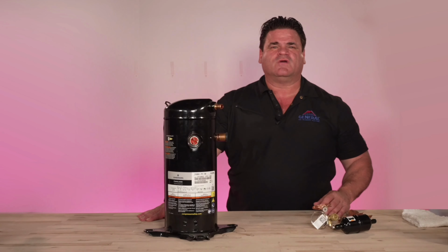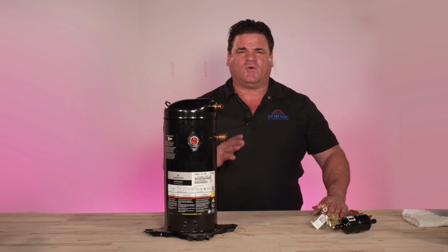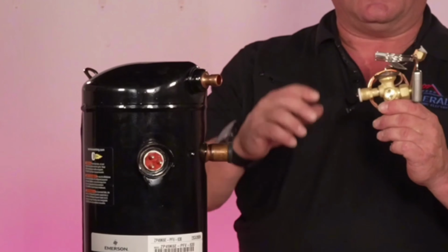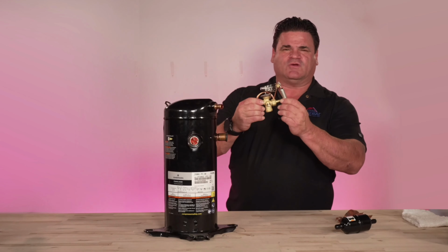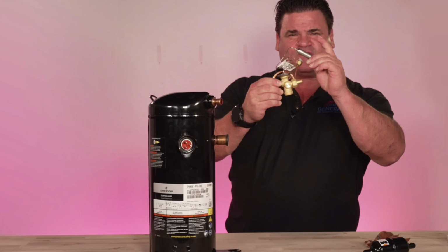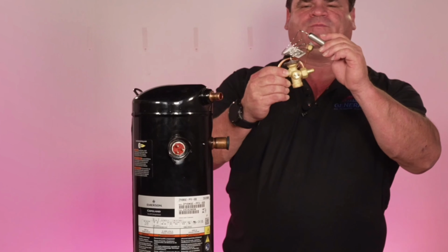I had an earlier video where I talked about an evaporator coil. How it gets into the coil is a TXV, thermal expansion valve. This is a TXV up close. I showed in an earlier video one that was installed, but this is the up close TXV. This here is what we call a sensing bulb. This actually has refrigerant in it. The same refrigerant that your system has in it is inside this bulb, all right?